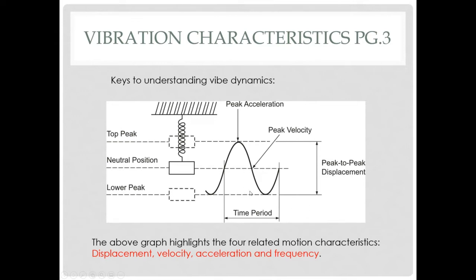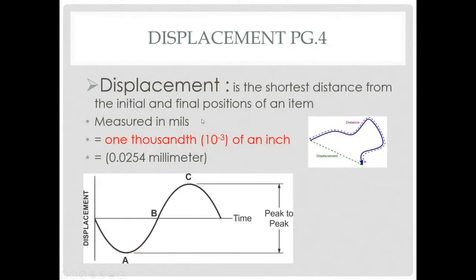These are called vector quantities because they measure certain changing measurements. When we measure vibration, we're talking about the interrelationship of all these different characteristics. The first characteristic is displacement. By definition, it is the shortest distance from the initial and final positions of an item. It is measured in mils — a mil is equal to a thousandth of an inch or 0.0254 millimeters. When we measure displacement, we're measuring the total amount that the object moves away from and towards the detector.